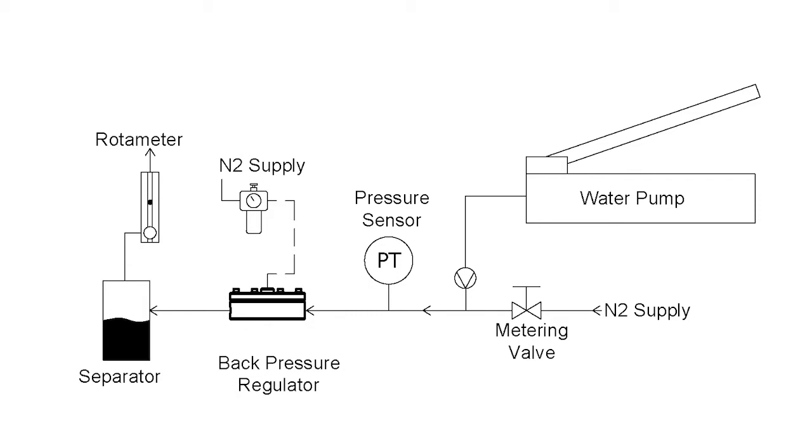The biggest difference here is that the Equilibar back pressure regulator utilizes a pneumatic set point instead of a spring to control inlet pressure. In this device the Equilibar controls inlet pressure with a one-to-one set point to reference. Let's go see how it compares in mixed phase flow.